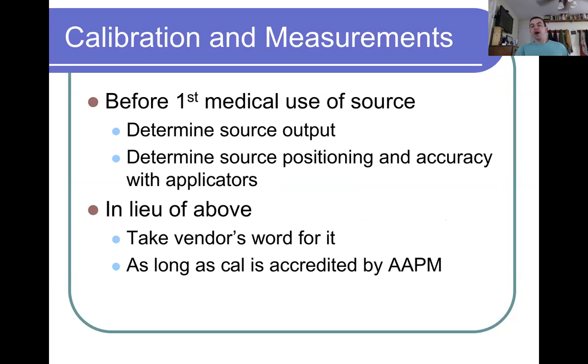We get seeds from the vendor that are calibrated. There's a certified strength on them, so you could trust the vendor. However, the brachytherapy group does do calibration on the sources prior to implantation. It's just seen as a prudent measure. Another set of eyes, another set of instruments on the source, just to make sure that we weren't accidentally sent a source that is maybe 10 times stronger or 100 times stronger, which could have a significant clinical effect once they're implanted. A permanent implant is not going to be easy to get out once it's implanted. So it makes sense for us, or for us as a whole at MSK, to measure the strength of the seed before they are put into a patient.